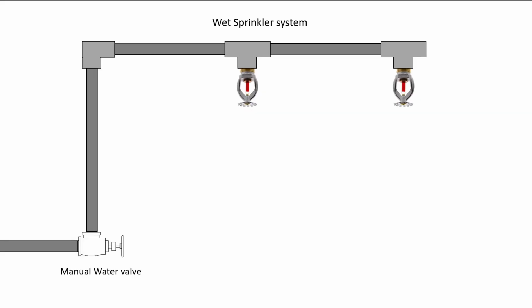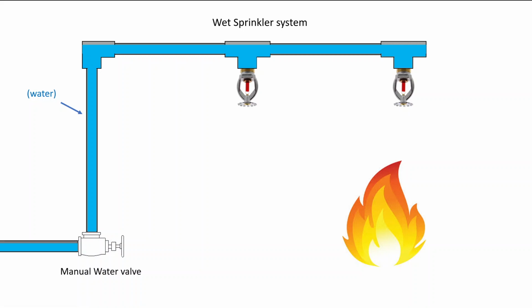The fire sprinkler pump might be used in a wet or a dry system. Let's take a look at how a wet system functions. A wet sprinkler system requires all of the piping to have water in it at all times. The sprinkler head sealing assembly and the little glass tube are the only thing that keep the water from coming out. During a fire event, whichever sprinkler head is nearest or has the temperature applied to it will burst, and sometimes it's one and sometimes it's all of them in the room. It kind of depends on the heat of that source.